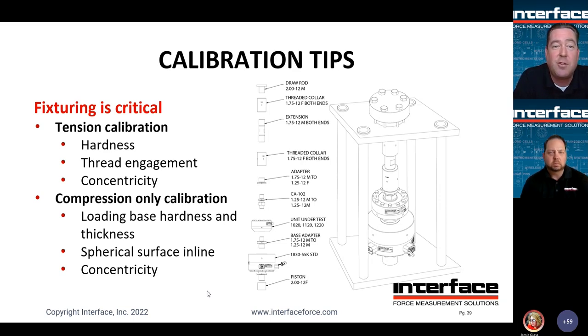So for tension calibration, some critical aspects to consider on fixturing. It's going to be the hardness of the material used, making sure it is of sufficient hardness, making sure thread engagement is sufficient. If you need to have a jammed nut against the load cell, that's very critical, making sure that the adapter in the load cell itself is jammed above the calibration capacity. And then, of course, making sure that that load string is concentric. If you have some sort of a misalignment or off-axis load, that will reflect at some level as an error in that calibration.